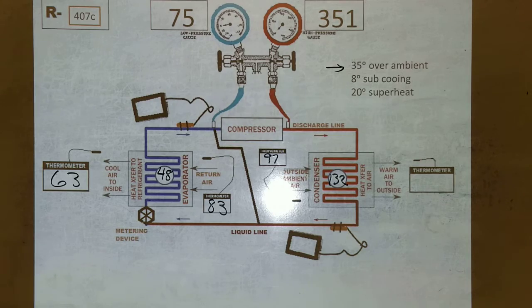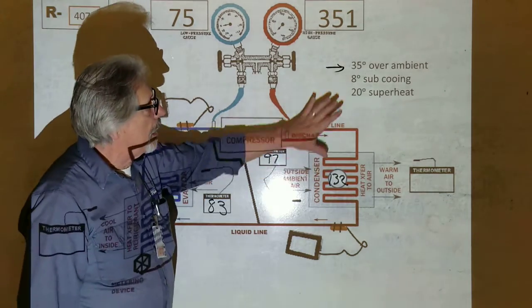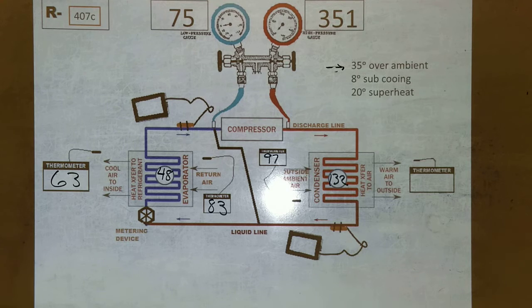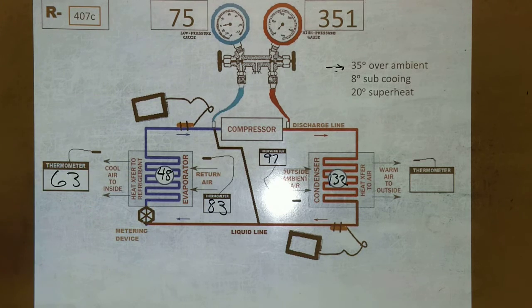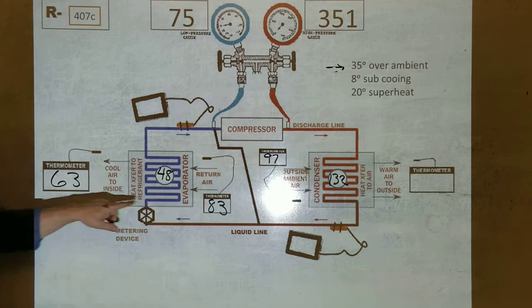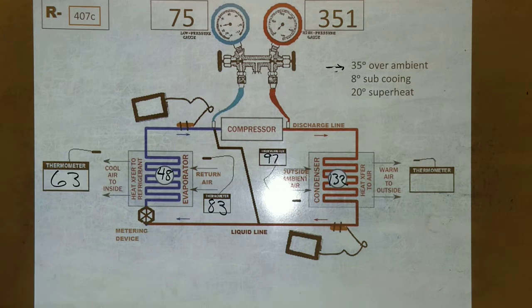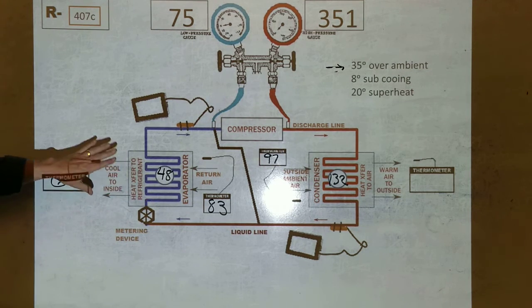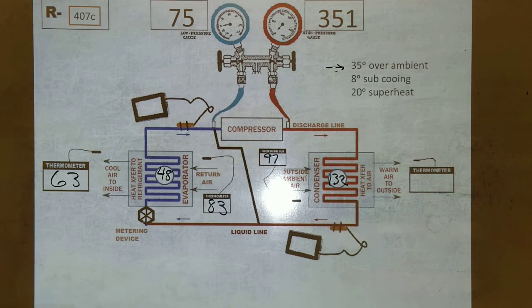But what we found out is since we can't go by the condenser high side and just add 35 and figure out what our high side pressure is anymore, it's just not possible with new high efficiency units. The only thing that didn't change is the indoor coil, which means what didn't change is comfort. Human comfort has not changed. So we're still gonna be comfortable at 75 degrees and 50% humidity, right? So in order to maintain that, this has gotta be consistent. So your split's gotta be consistent and your approach has gotta be consistent. So now we can look at the low side of the system and find out if our charge is correct, on older units and newer units.